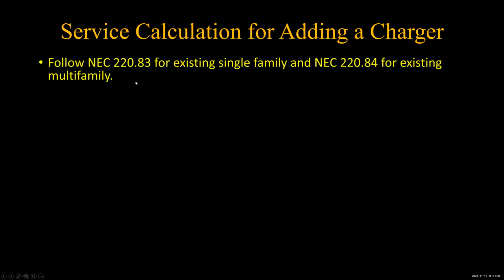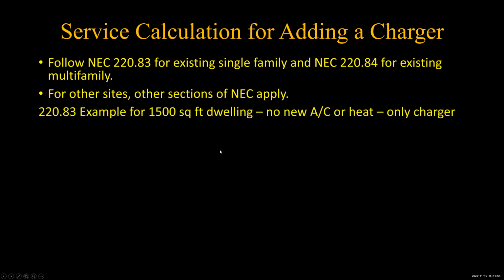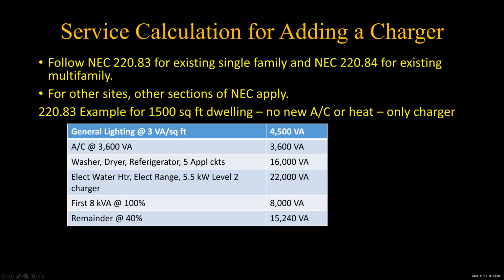All right, if you're going to add a charger, Article 220 tells you how to calculate the service size for a single family dwelling in 220.83. And if you have an existing multifamily dwelling, 220.84 tells you how to run that calculation. And there are other sections of the National Electrical Code for commercial and so on. But let's do the 220.83 example. Let's say we have a 1,500 square foot dwelling, no new air conditioning, no new heat, we're just going to add a new charger to it. So let's do the calc.